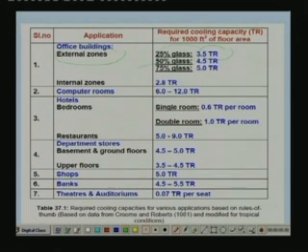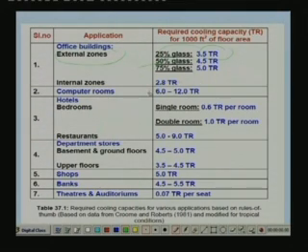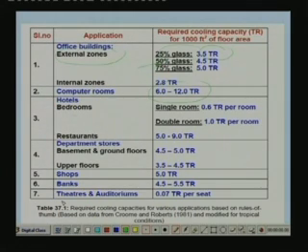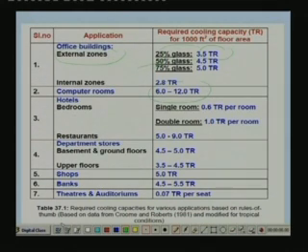If the percentage of glass is 50 percent then the required cooling capacity is about 4.5 tons. For computer rooms the required cooling capacity lies between 6 to 12 tons per 1000 square feet of floor area. Similarly for other applications like hotels, bedrooms, departmental stores, shops, banks, and theatres. These values are based on many years of experience — this is what is known as estimating cooling capacity based on rules of thumb.